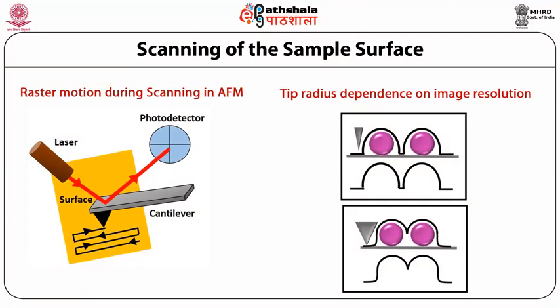Scanning of the sample surface. The tip passes back and forth in a straight line across the sample. In a typical imaging mode, the tip sample force is held constant by adjusting the vertical position of the tip. The tip is brought within nanometer range of the sample. A topographic image is built up by recording the vertical position when the tip is rastered across the sample using a computer, as shown in figure 11.